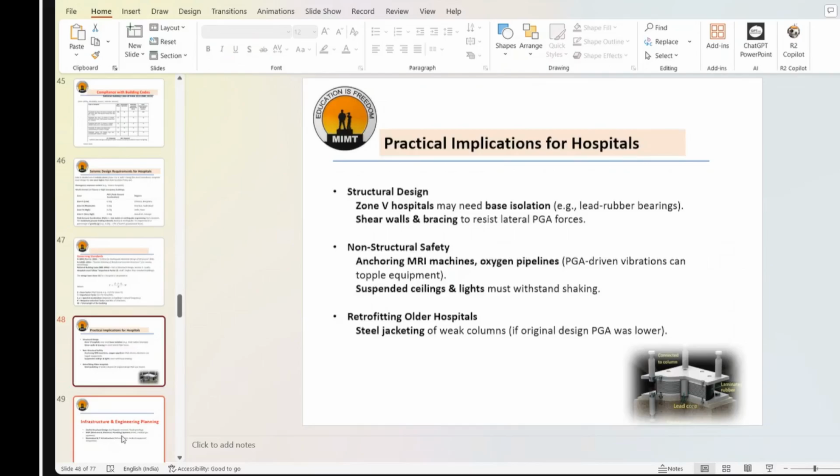तो इनकी भी हमें एंकरिंग, that is supposed to be done based on this seismic activity. यदि जोन फोर्थ में तो ऐसा नहीं होना चाहिए कि जरा सा भी हल्का सा मूवमेंट आने से, पीजीए बढ़ने से आपकी जो मशीनें हैं, they start crumbling, they start falling down, something like that. So based on that seismic zone, you have to ensure you do anchoring of this machine, investigation machines or various other things. They are supposed to be taken care of in that manner.